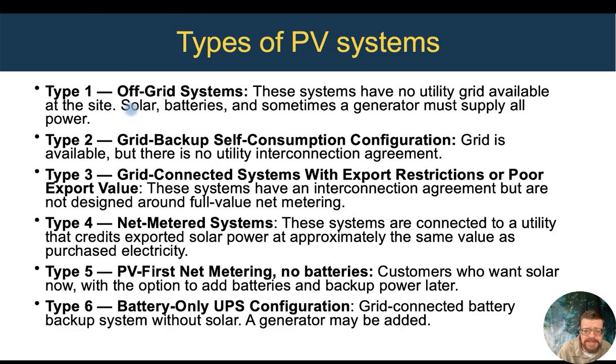These are kind of our 6 main types of PV systems that we can do with this inverter. Like we mentioned before, type 1 is off-grid systems, if there's just no utility grid at all. Type 2 is when we do have the utility grid, but we don't have an interconnection agreement. So we're really using the utility grid more like we would use a generator in an off-grid system. We're not interacting with it very much, except to use it as a backup power source if the solar is insufficient. Type 3 is grid connection systems, but no net metering.